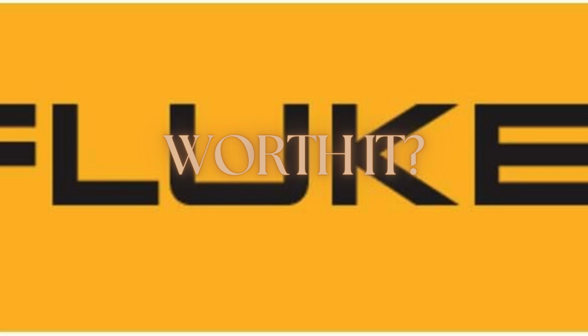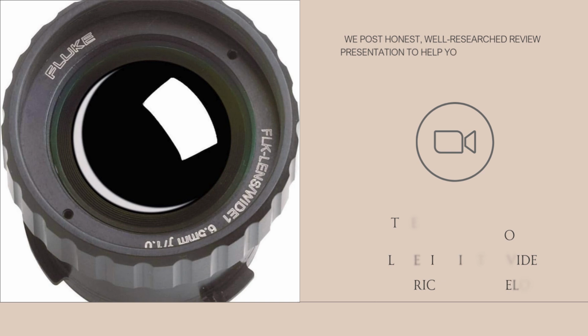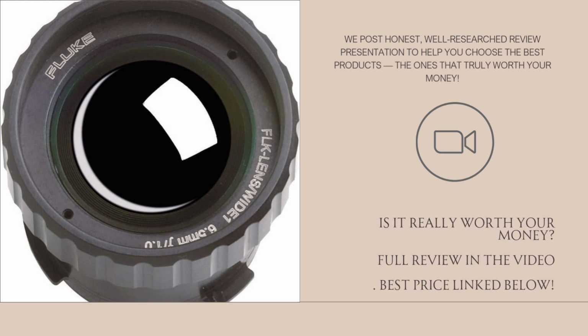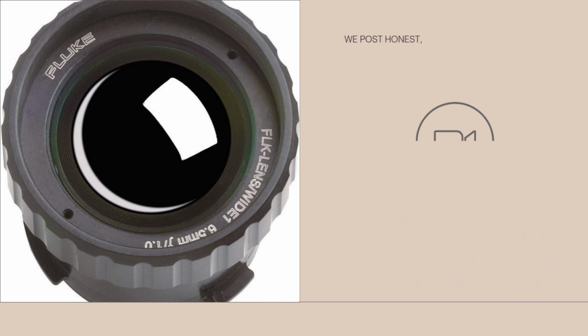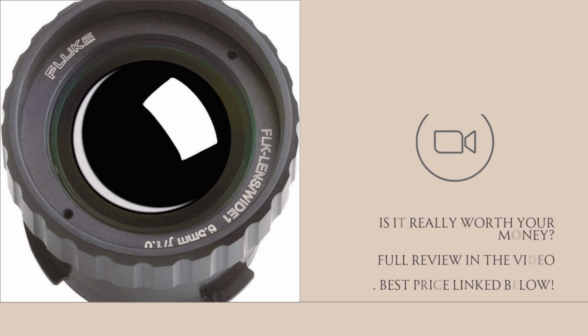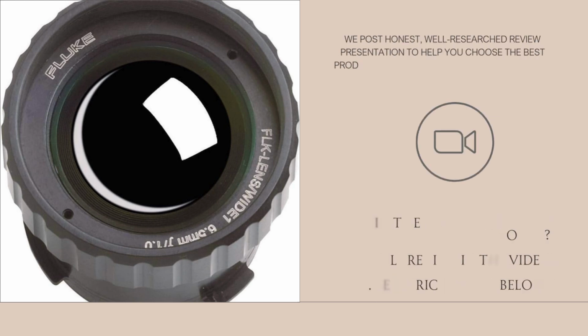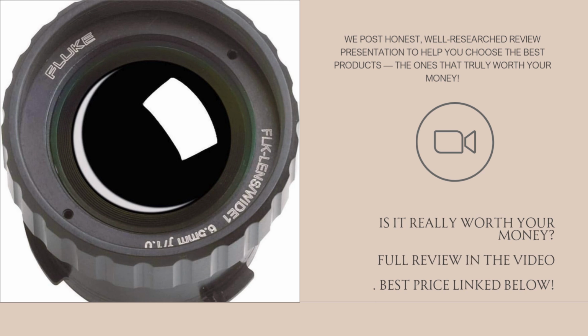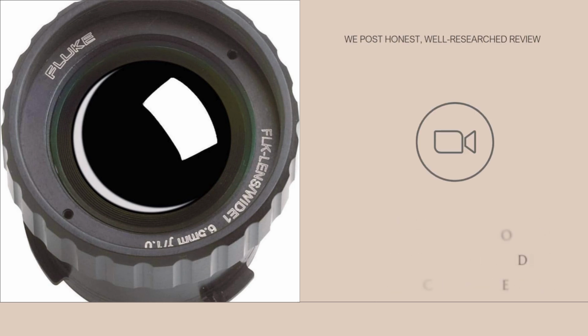Third, in very low ambient temperature situations or extreme IR scene contrast, the lens may introduce slightly more vignetting or require careful focus adjustment given the short minimum distance. And fourth, for very narrow or long-distance tasks, you might still prefer a telephoto or standard lens rather than the wide angle. So, is it worth the investment?